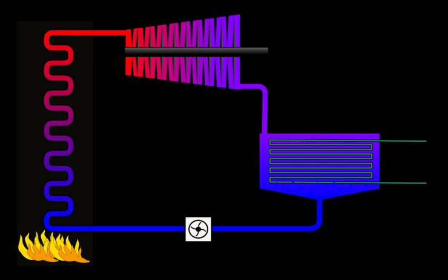By condensing the working steam vapor to a liquid, the pressure at the turbine outlet is lowered and the energy required by the feed pump consumes only 1% to 3% of the turbine output power and these factors contribute to a higher efficiency for the cycle. The benefit of this is offset by the low temperatures of steam admitted to the turbines.